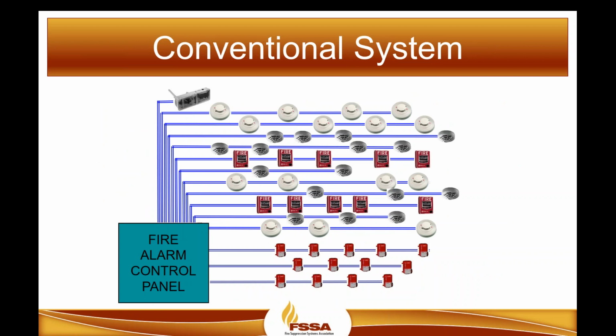Yeah, absolutely, Dan. And these are really the heart of our smaller systems in special hazards. They're a typical conventional fire alarm panel that's been modified, tested and approved for releasing. They're fixed power-limited circuitry, typically on one board, including the initiation, NAC, releasing, supervisory circuits, and Form C relays, all on one board. They also have constant and typically resettable 24 volt aux power for either optical flame detection, resetting, or duct detectors.